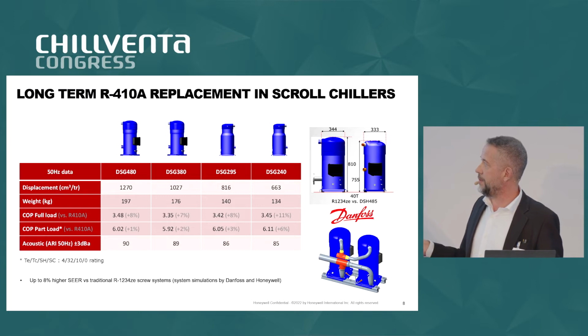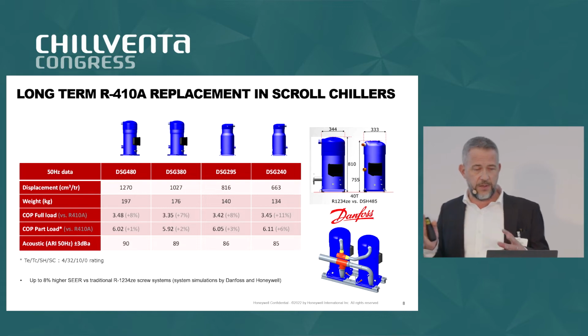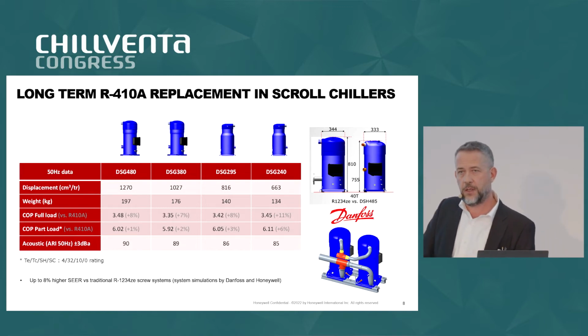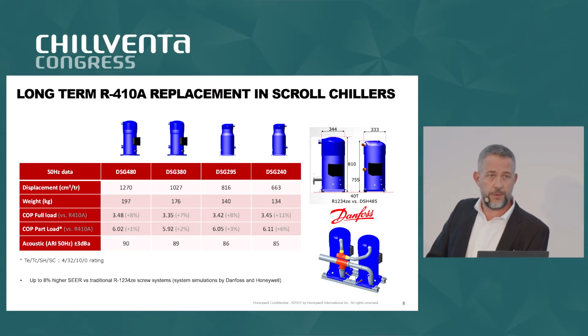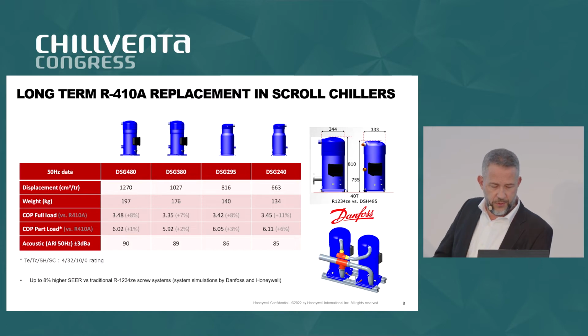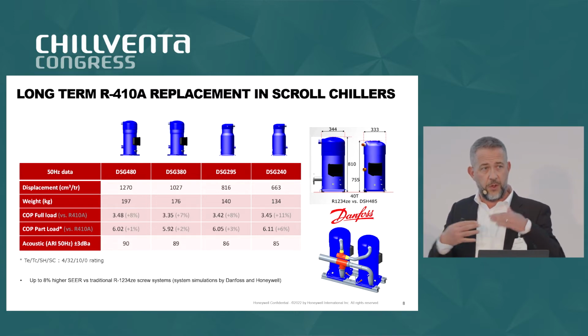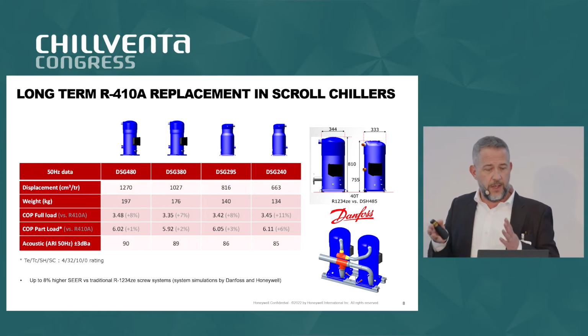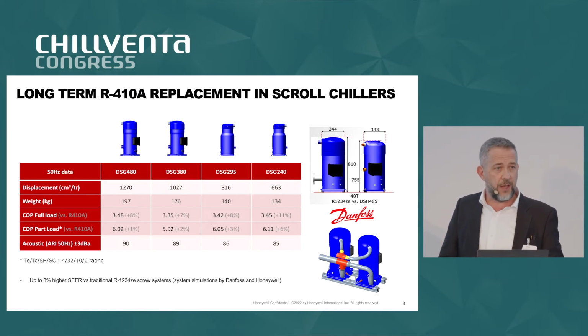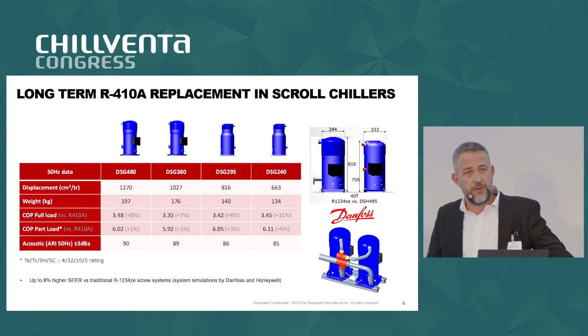In partial load it's increasing as well, not in the same range, but on a seasonal efficiency scenario you'll win a lot. We did a comparison of seasonal efficiency at the system level, internal Honeywell and Danfoss modelization, comparing to screw systems in the small range where there's overlap between scroll and screws. We're somewhere around 8% higher seasonal efficiency versus screws.